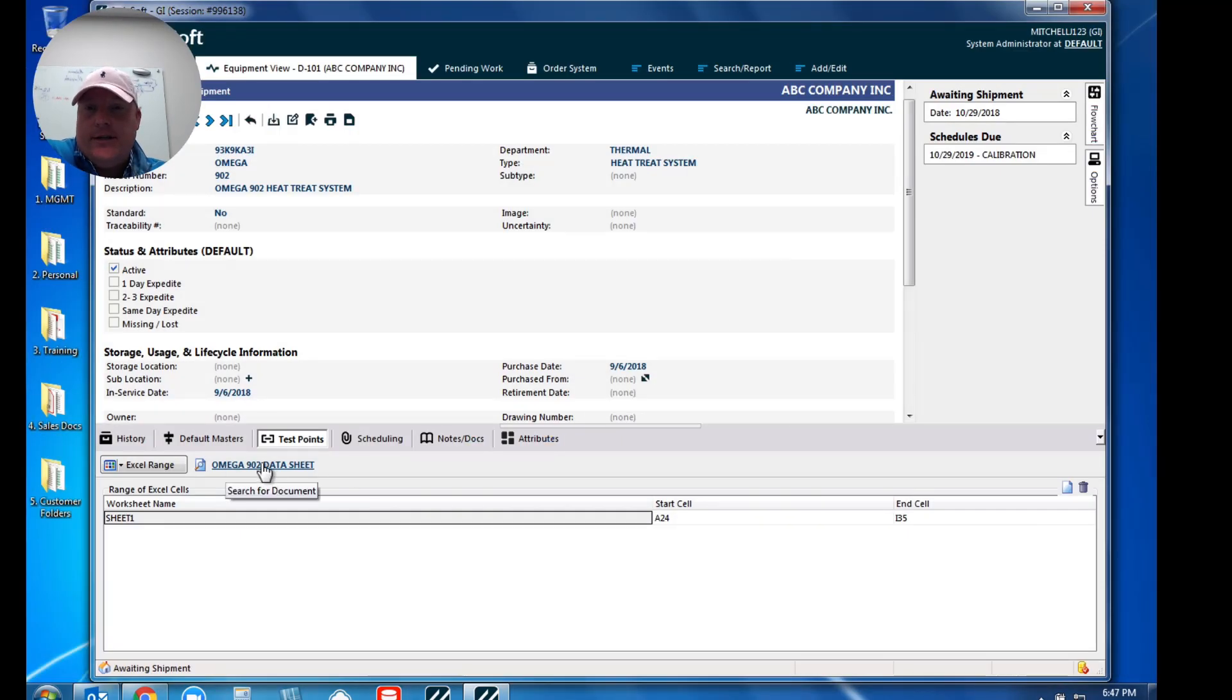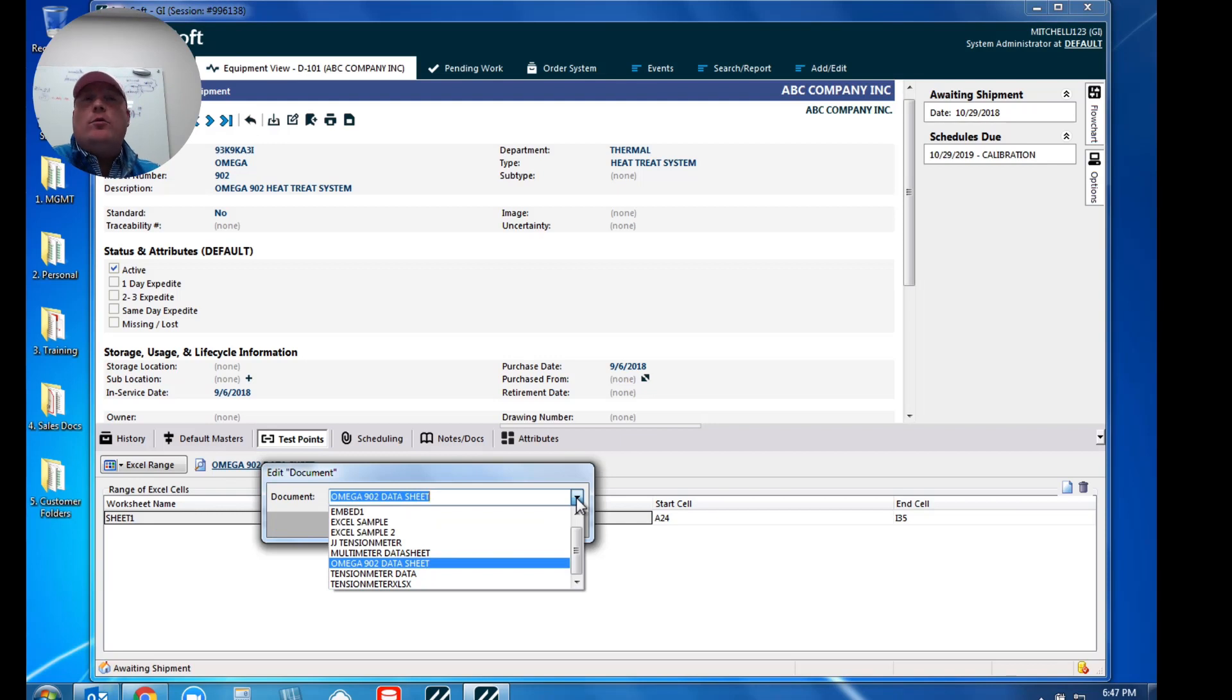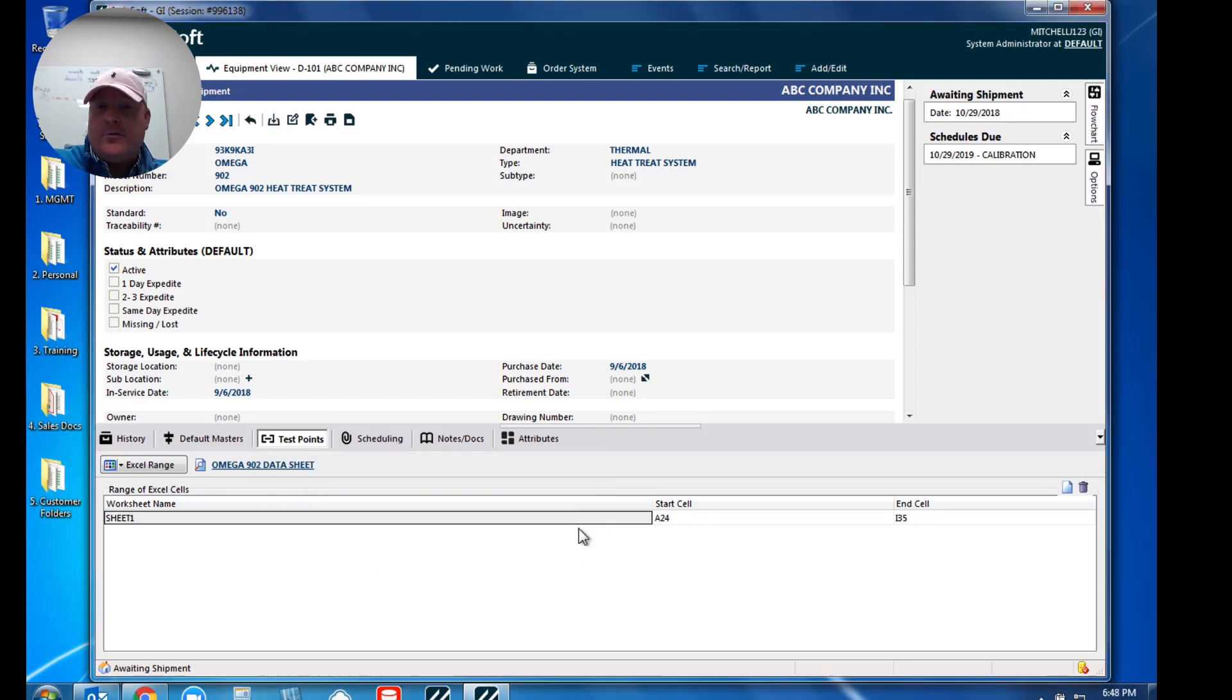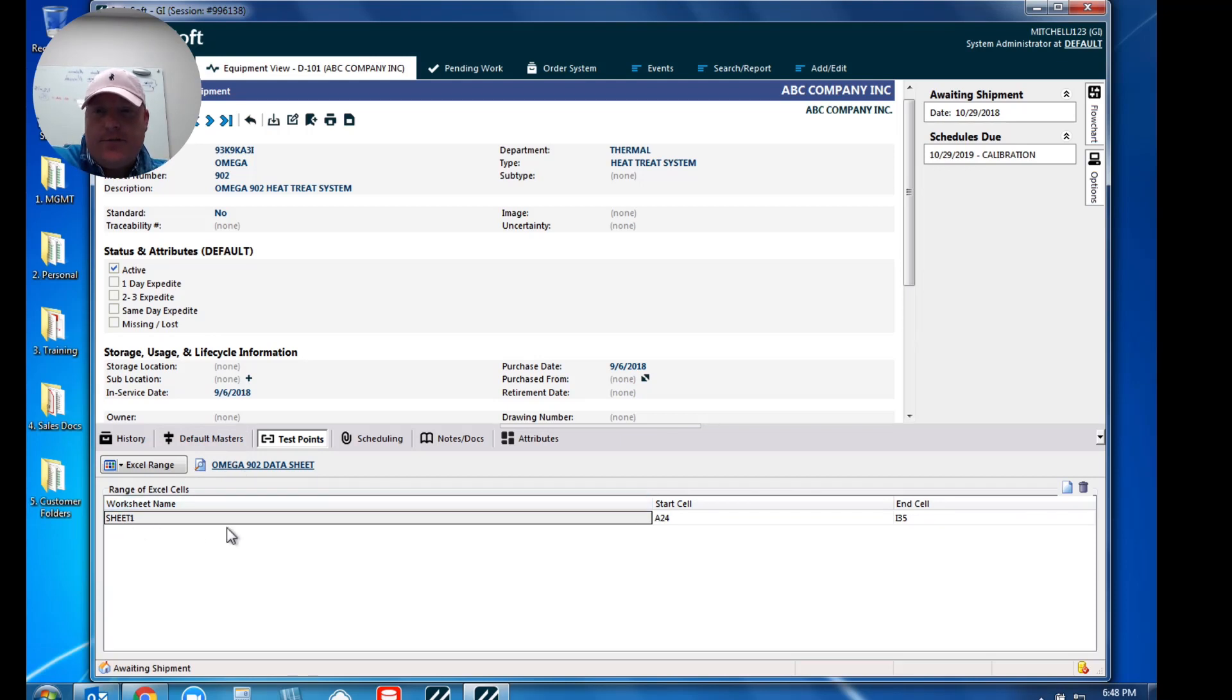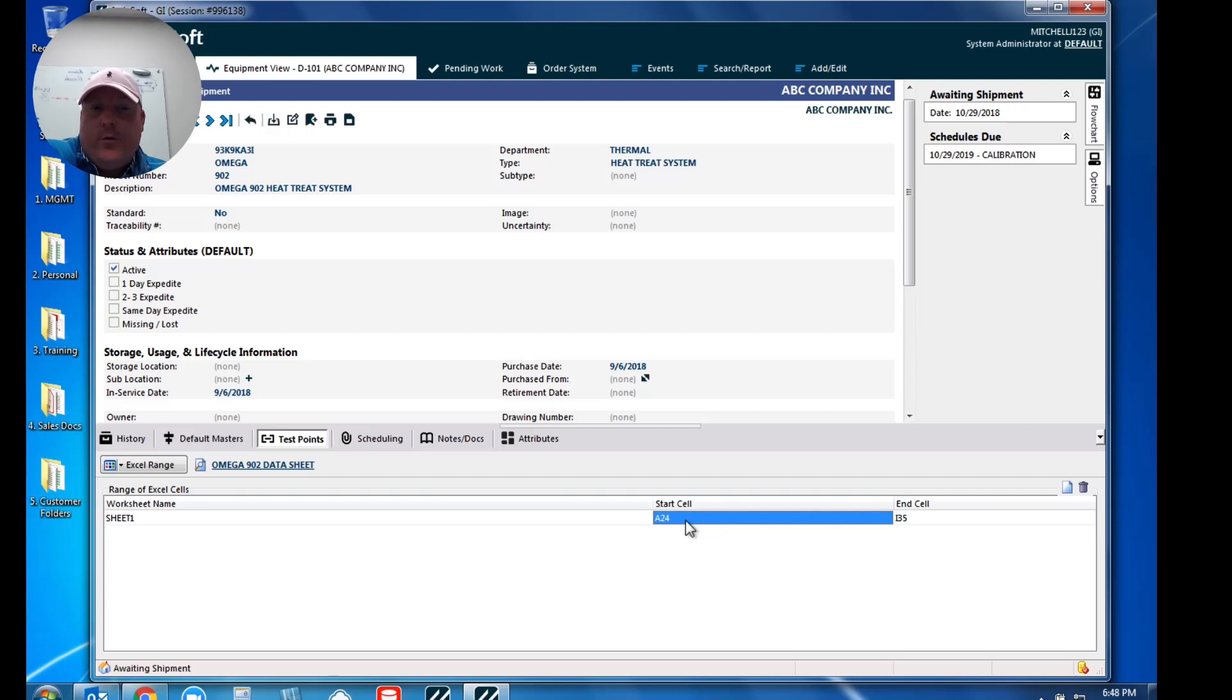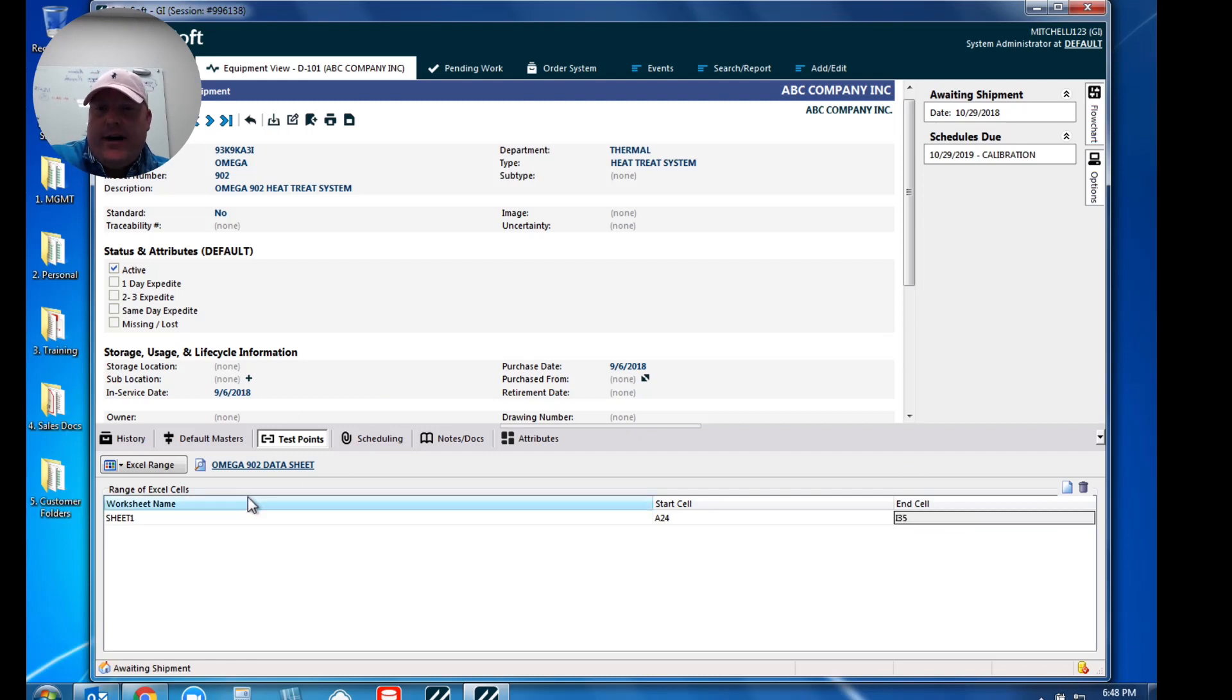When I open this up, you'll see there's that data sheet, which this is a more simpler data sheet of course. What you'll also notice is there is a drop-down list so you can have multiple different types of data sheets here. So you may have like a gauge block layout, in this case an Omega 902, or maybe you have some type of a multimeter spreadsheet as well. But once you have your data sheet specified for this particular instrument, you'll then specify which chunk or which section of that Excel certificate do you want to embed within to the IndySoft generated PDF. So in my case, I want sheet one and I want cells A24 through I35.